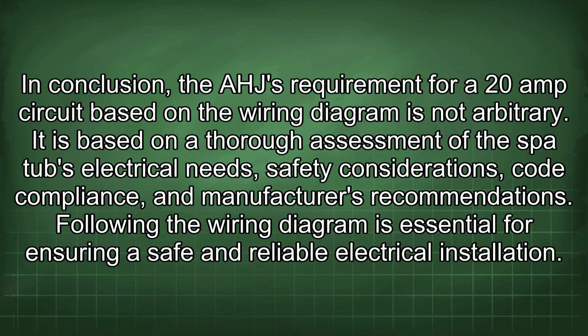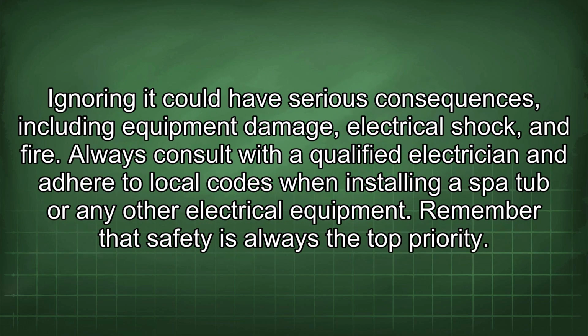In conclusion, the AHJ requirement for a 20 amp circuit based on the wiring diagram is not arbitrary. It is based on a thorough assessment of the spa tub's electrical needs, safety considerations, code compliance, and manufacturer's recommendations. Following the wiring diagram is essential for ensuring a safe and reliable electrical installation. Ignoring it could have serious consequences, including equipment damage, electrical shock, and fire. Always consult with a qualified electrician and adhere to local codes when installing a spa tub or any other electrical equipment. Remember that safety is always the top priority.